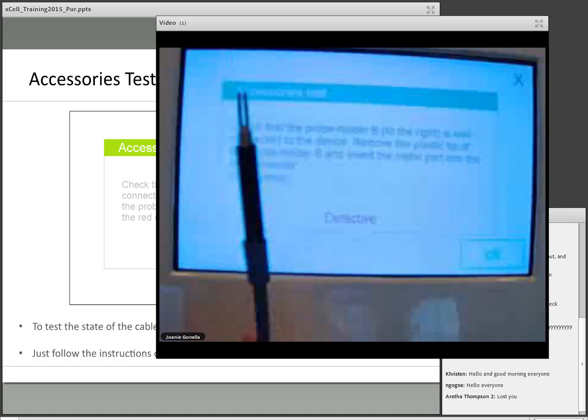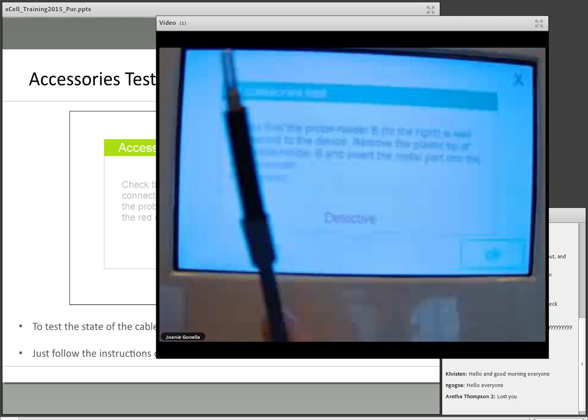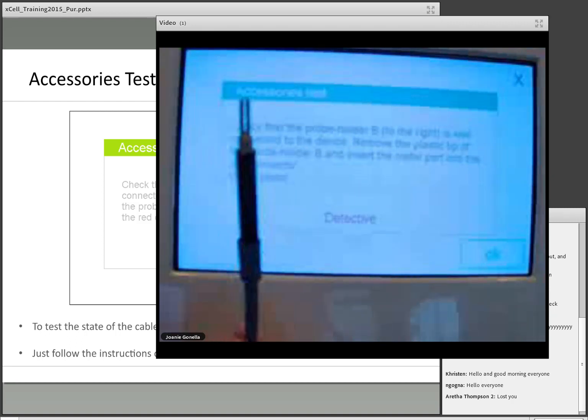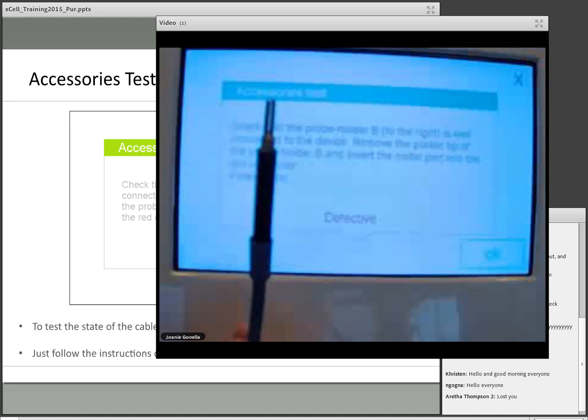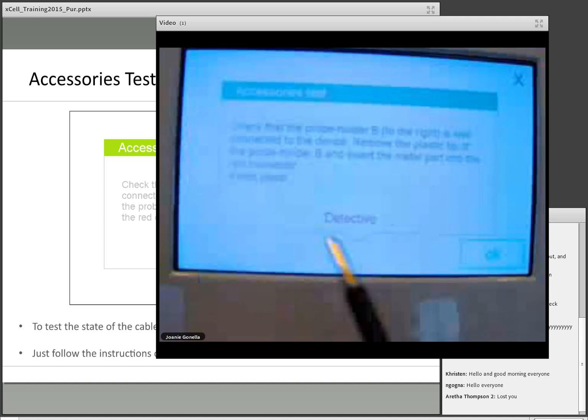Essentially the machine sent a current down the probe, and it was looking for it to come back so that it could make sure that what it sent, it received back. Because I didn't have this connected into the machine, it just went nowhere. So it tested that as defective. You would have to actually have it plugged into the machine where we had it before in order to see it as functional.